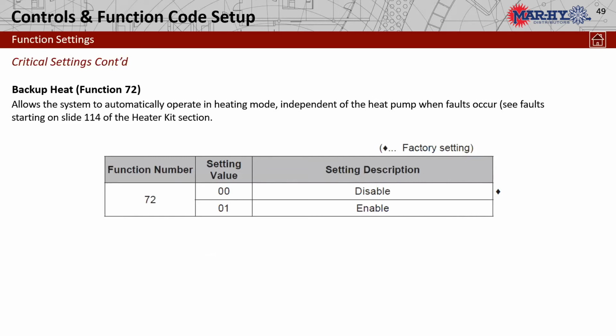Function 72. This is backup heat. This is for operation of our strip heaters. If you do have backup heat, you do want to use this function. What this will do is turn the strip heat on anytime we have an outdoor lockout. If we have any faults that occur in the outdoor unit, in the heat pump, that enable it not to operate, it will automatically switch to strip heat operation. So if you have strip heat installed, enable this function.